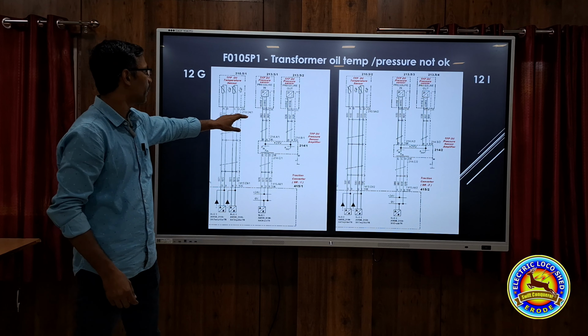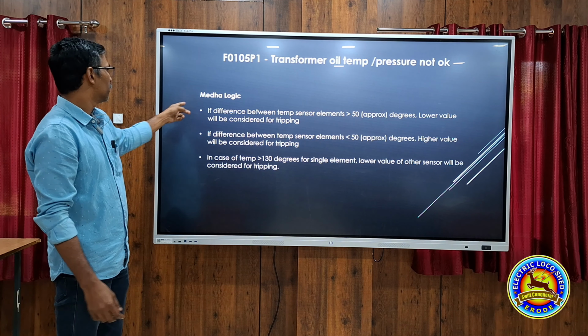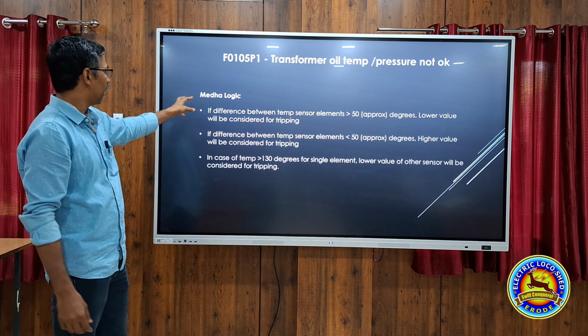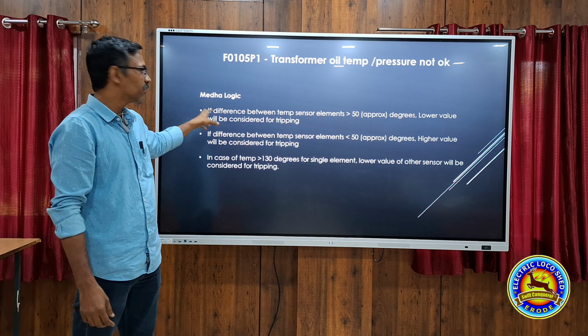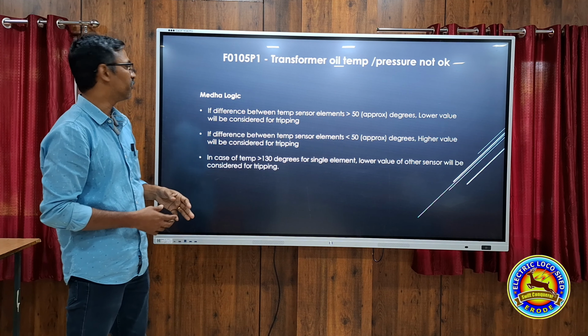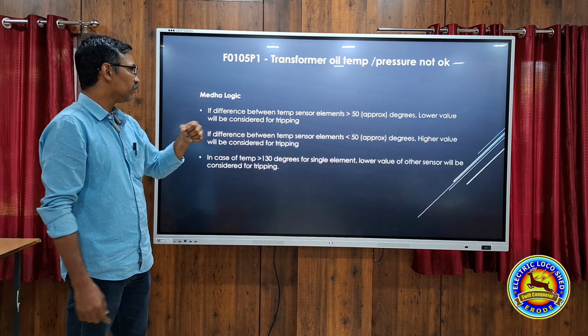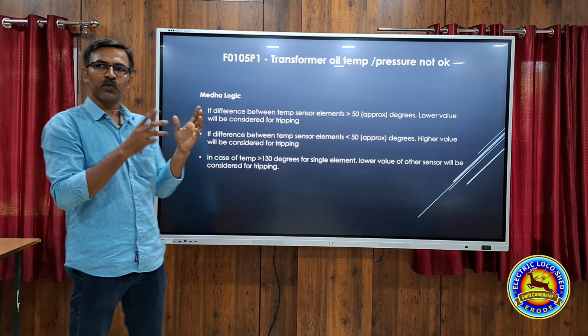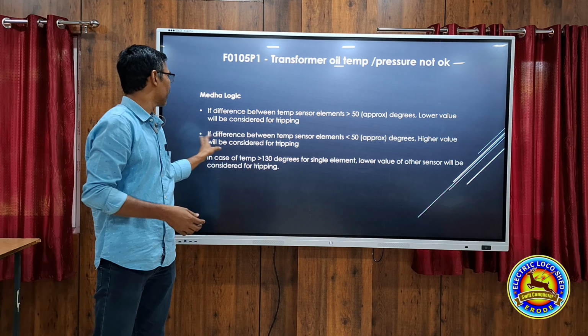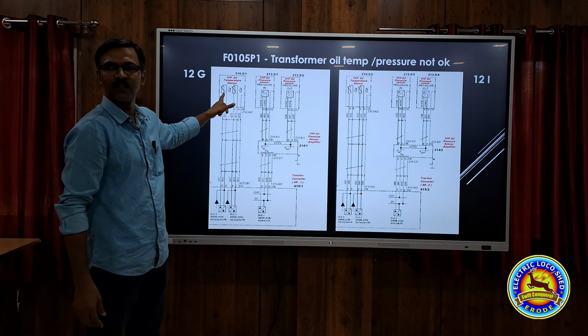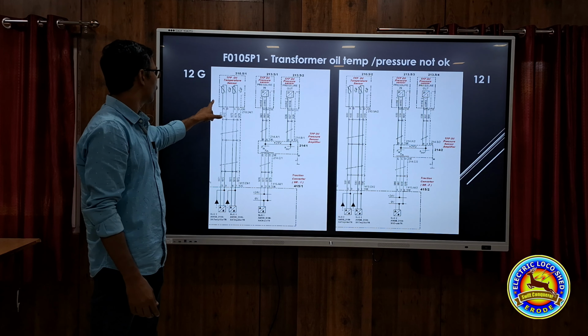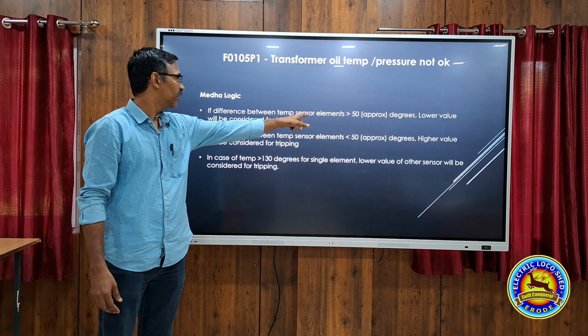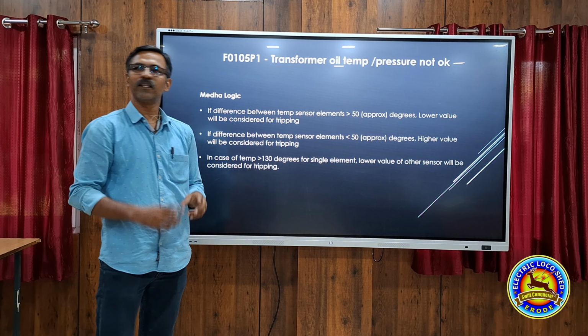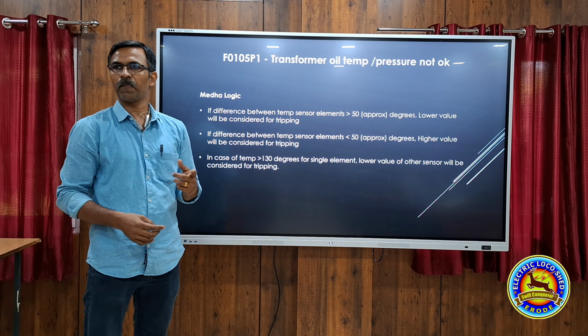So when will this fault come? We can see the logic. I put the logic of MEDA propulsion, and BT is also almost similar. ABB is somewhat different. If the difference of the two elements, I told you there are two elements in a single sensor, is more than 50 degrees, the lower value will be considered for DJ tripping.